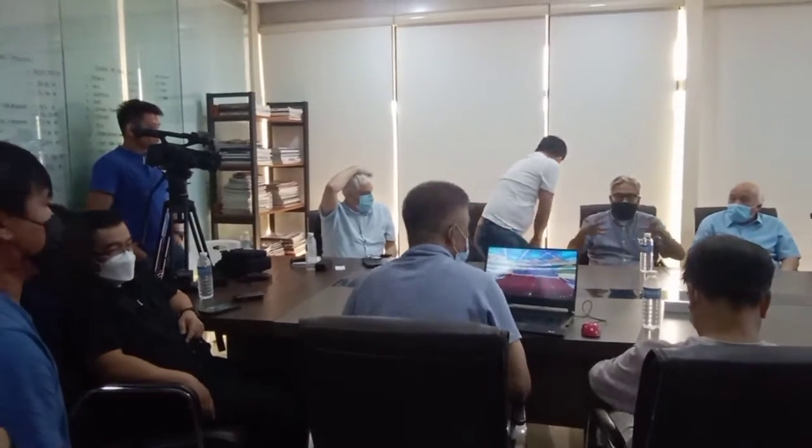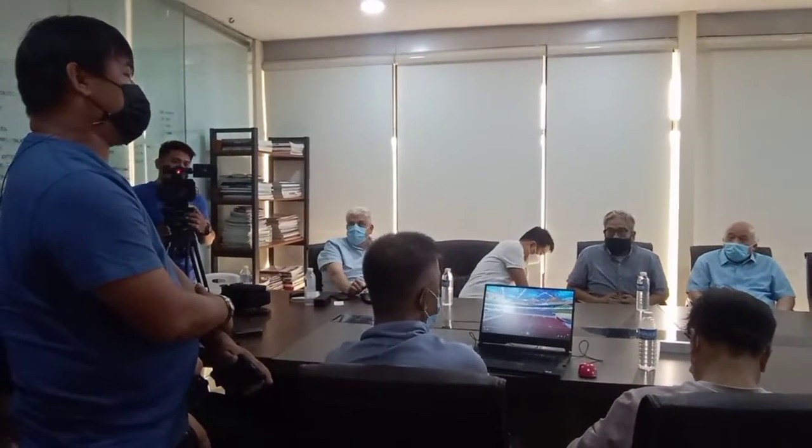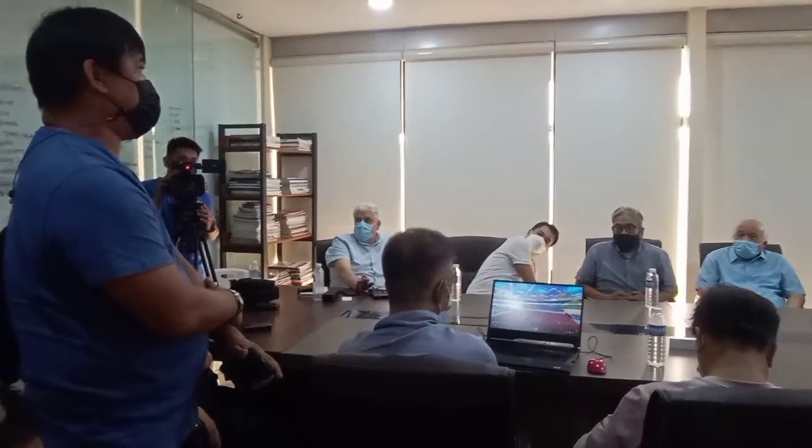Correct. So all of this we can take a look at and make recommendations. And lastly, sir, I understand that there is a sound attenuator. We discussed it. As much as possible I try to limit it, because right now we are trying to attain at least 11 to 12 meters per second face velocity. And in order to accomplish that for 200 tons, even though the US manufacturer said it cannot be made, that's the reason why right now, if I am using a sound attenuator, at the end of the farthest distance, the pressure drop I have is very big.